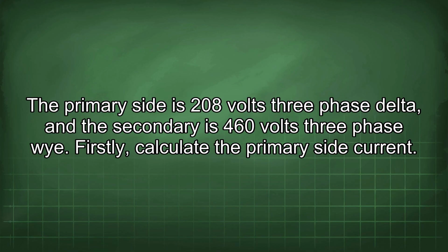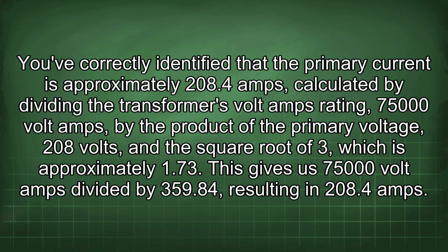Firstly, calculate the primary side current. You've correctly identified that the primary current is approximately 208.4 amps, calculated by dividing the transformer's volt-amps rating, 75,000 volt-amps, by the product of the primary voltage, 208 volts, and the square root of 3, which is approximately 1.73. This gives us 75,000 volt-amps divided by 359.84, resulting in 208.4 amps.